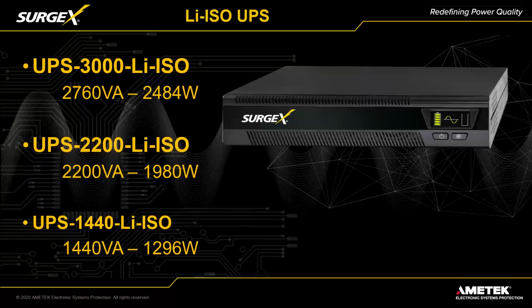Obviously, to use the 30 amp piece, we're going to need a 30 amp breaker and a 30 amp wall outlet to power this 3000 VA unit, or 2760 is the actual spec. The 2200 piece will be a 20 amp rated product. You're going to have a 20 amp circuit and a 20 amp wall outlet. Make sure you've got both of those. And then the 15 amp will work with that NEMA 15 that most of us are pretty comfortable with. And the input connector on this one is an IEC, a removable or detachable cord with an IEC type connector.